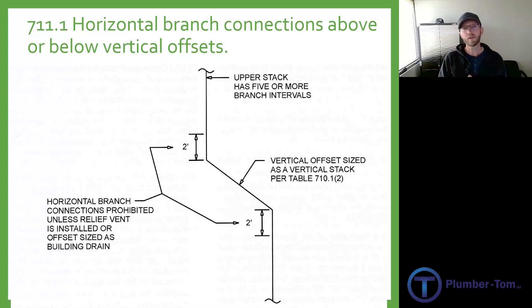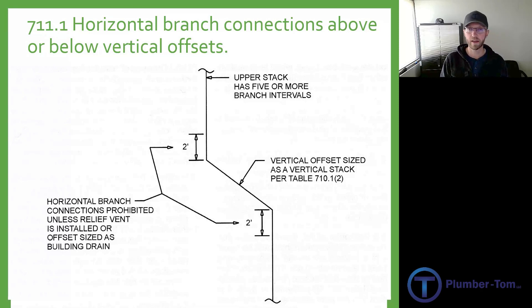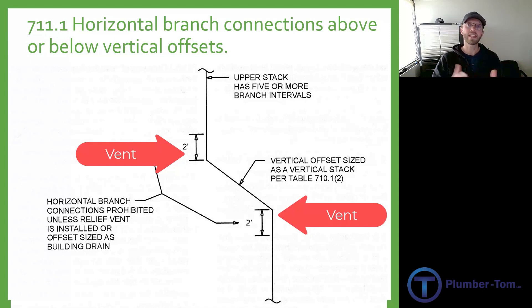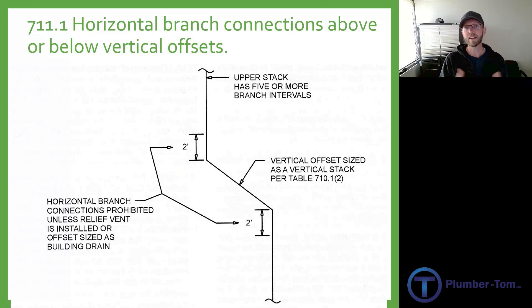There is another note in 7-11.1.1 which talks about omission of vents for vertical stack offsets. When we get into chapter 9 we learn that these offsets need vents to help them breathe and help that flow. But this omission of vents refers to the option that you can just increase the size of the pipe. If you size it as a building drain it's going to be bigger, which gives more airflow inside of it and you would not need to provide vents.